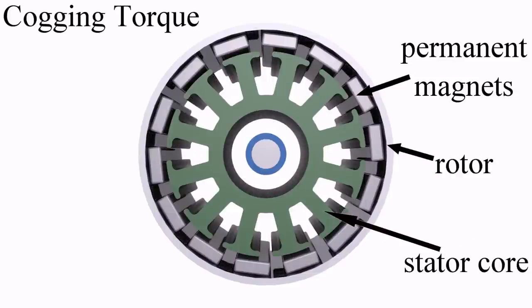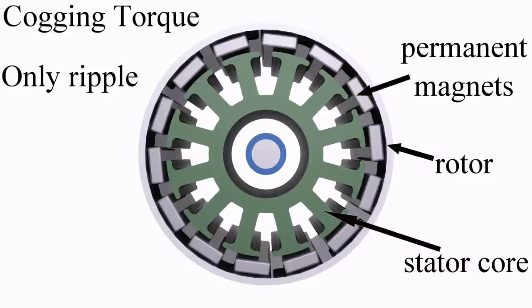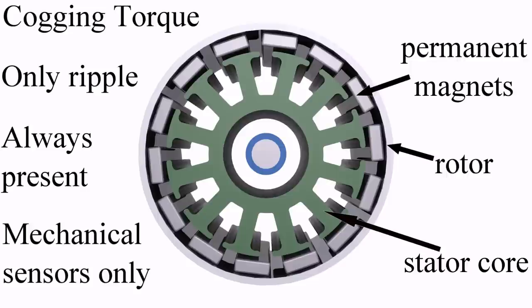Cogging torque, also called detent torque, is when the permanent magnets attract the motor's core. Unlike mutual and reluctance torques, cogging torque cannot make the motor spin continuously, only contributes to torque ripple, is always present, and is only detectable by mechanical sensors.